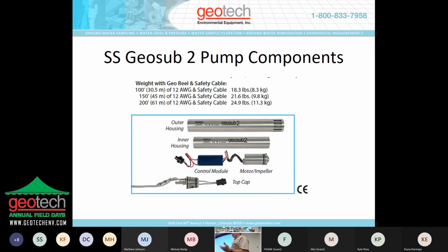Some of the components I mentioned earlier, all these pumps require maintenance. They're configured differently. The SS GeoSub 2 is a DC motor, but it's not like a DC motor that you would find on a little fan that you buy at the convenience store. It actually has a control module that conditions the power. And you'll notice it goes from 2 wires, and you can't really see it in the photo here, but it goes to 3. This is a very high performance, high speed motor. So that conditioning module is what moderates the power to feed that motor. As an assembly, those 2 items are a wear part.